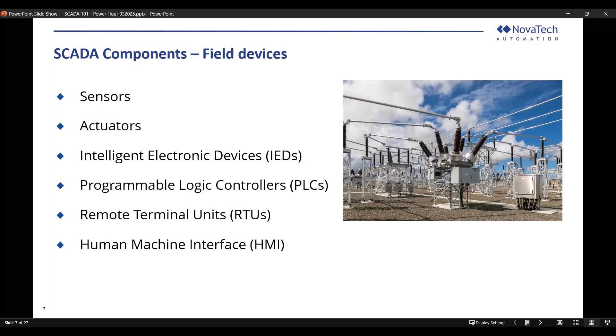Another thing I want to bring up is SCADA. I always thought SCADA was just the top level, but SCADA systems actually consist of the entire system, including the field devices we just mentioned. One critical thing is: how do I get data from point A to point B? This is your communication infrastructure, the backbone of a SCADA system. If there's no communication infrastructure, there's no SCADA system. Your SCADA software at the top is kind of useless if there's no data coming into it.